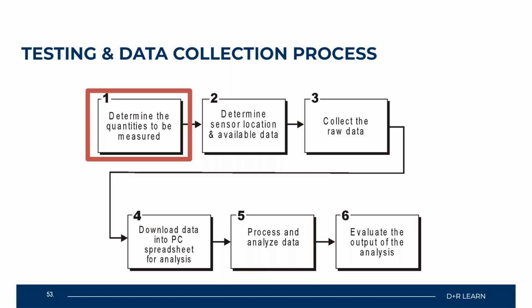Now, the data loggers are extremely important in this case because when it comes to running your operation, you want to be as efficient as possible. In order to do what these systems and sensors are able to do, you would need to have personnel on site 24 hours a day. Your data loggers run continuously and transfer that information to a PC database for review, evaluation or diagnosis at a later date. So whether that is you running a sensor retrieval report so you can see what's happening with the system's load efficiency, and you want to run that for the evening hours while no one is on site, you have the ability to do that through the use of testing and data collection processes by using sensors and BAS systems.